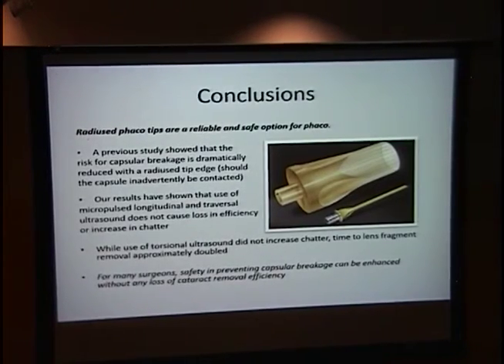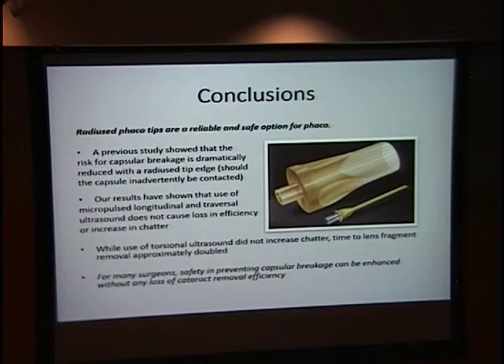In conclusion, radius phaco tips are a reliable and safe option for phacoemulsification. A previous study showed that capsular breakage is dramatically reduced with this radius tip. In this study, we were able to show that in certain ultrasound models — specifically longitudinal and transversal — you do not lose any efficiency or have an increase in chatter. This is very important in the field, because for many surgeons this could be something they could employ right away to increase safety and maintain efficiency.